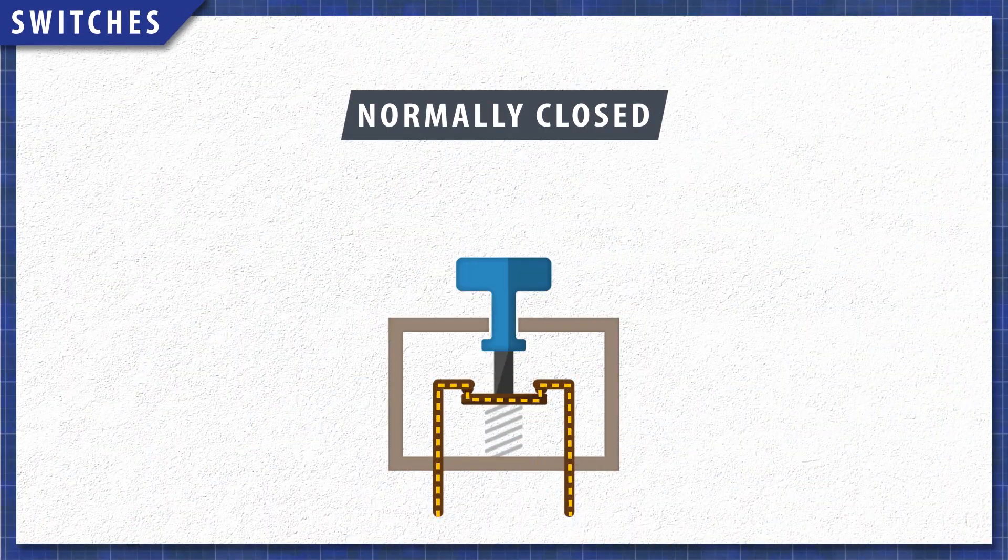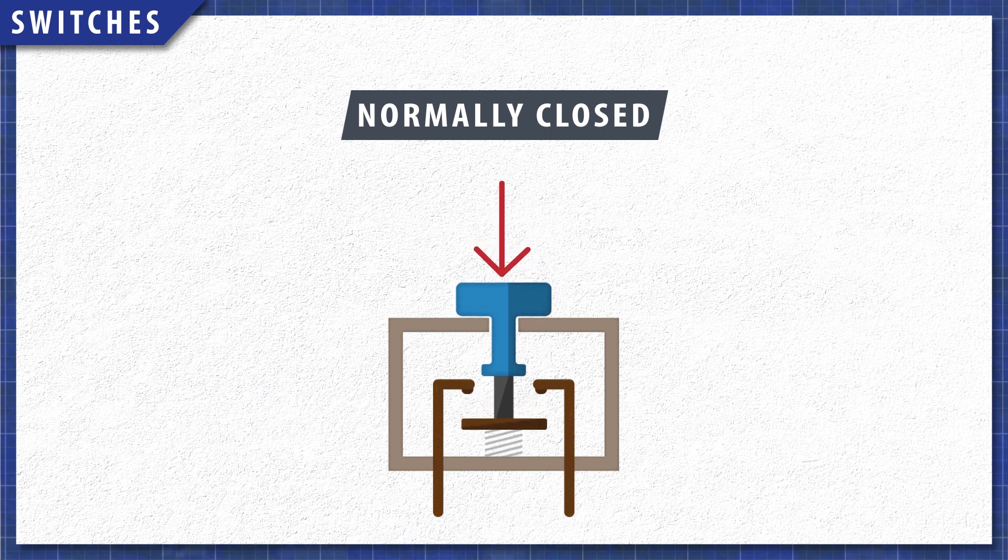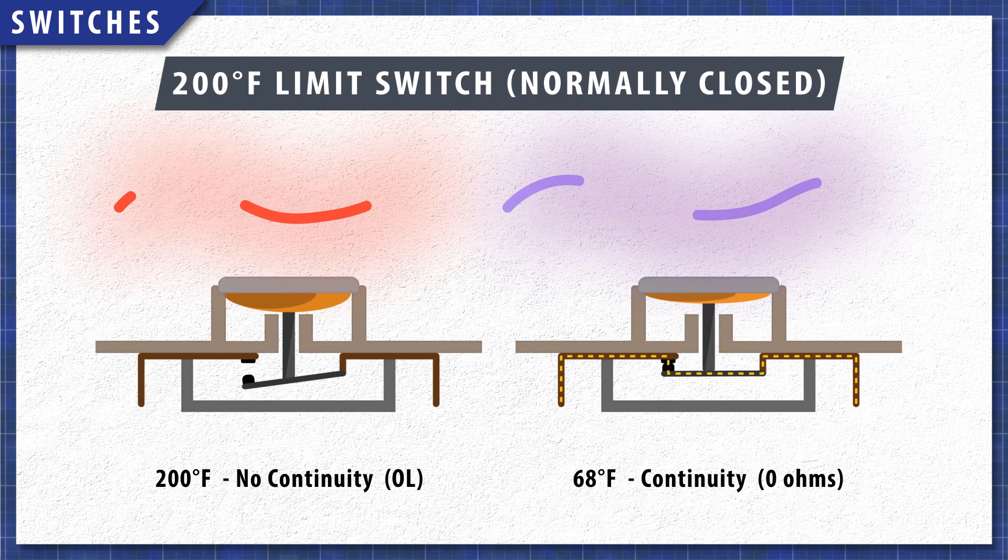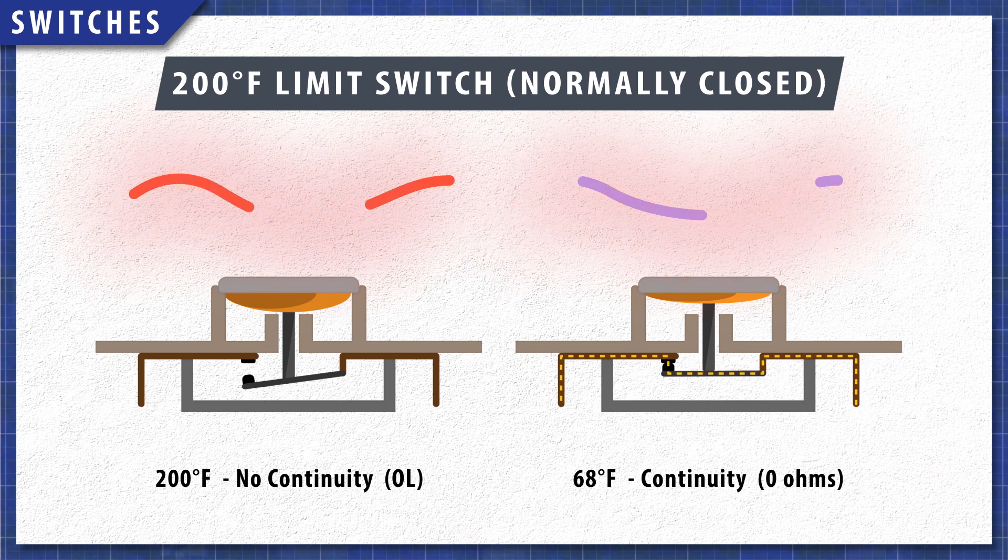Normally closed switches have continuity until the switch is opened. One example is a high limit switch rated to open at 200 degrees Fahrenheit, which will have continuity at room temperature.